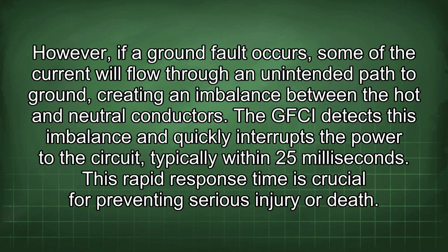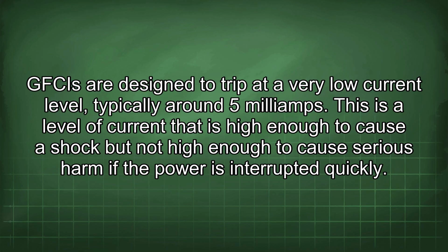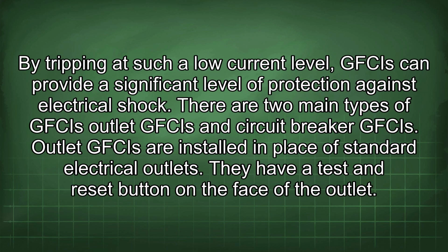However, if a ground fault occurs, some of the current will flow through an unintended path to ground, creating an imbalance between the hot and neutral conductors. The GFCI detects this imbalance and quickly interrupts the power to the circuit, typically within 25 milliseconds. This rapid response time is crucial for preventing serious injury or death. GFCIs are designed to trip at a very low current level, typically around 5 milliamps. This is a level of current that is high enough to cause a shock but not high enough to cause serious harm if the power is interrupted quickly. By tripping at such a low current level, GFCIs can provide a significant level of protection against electrical shock.